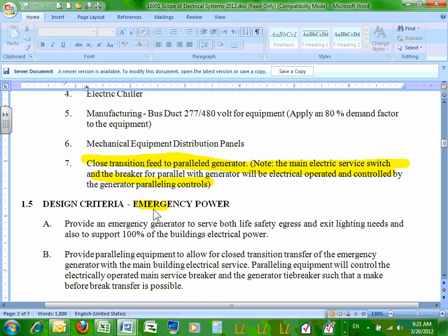But what I'm talking about here is within my switchboard, I'll just draw it simple. Maybe my initial cube might have a large circuit breaker, and then maybe in the next cube, I might have a large circuit breaker. This may go to the gen. This may go to my utility. So I have paralleling equipment controls within this board that looks at the generator and looks at the utility. So normally, of course, I'm running on utility, generator's not running. This breaker's closed, this breaker's open, and life is good.